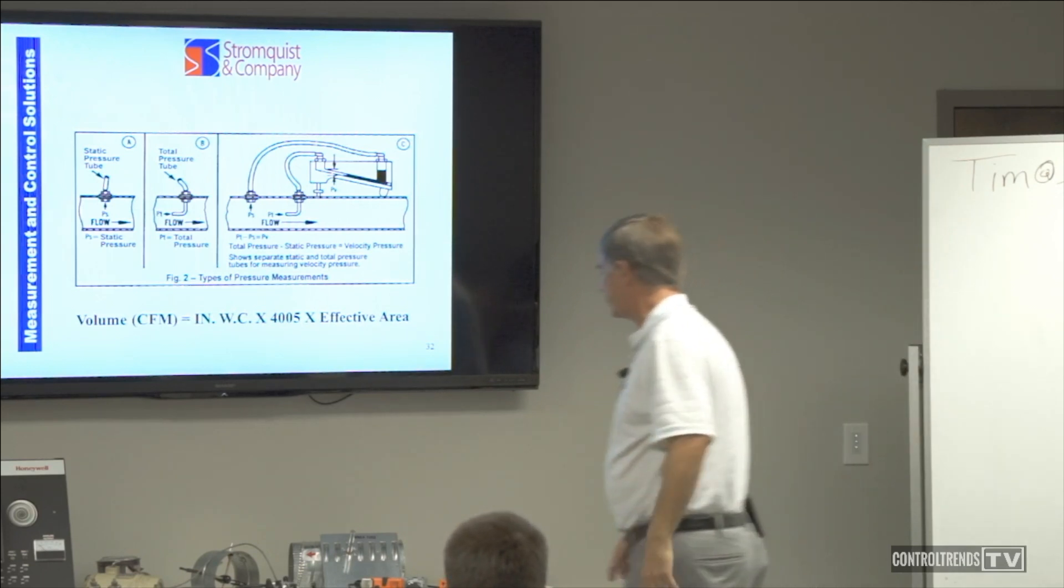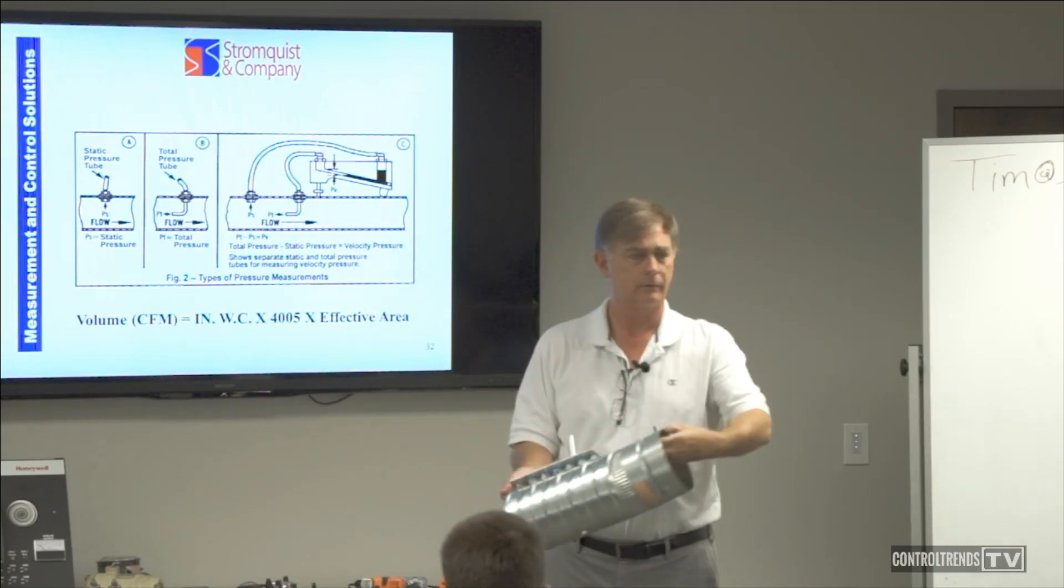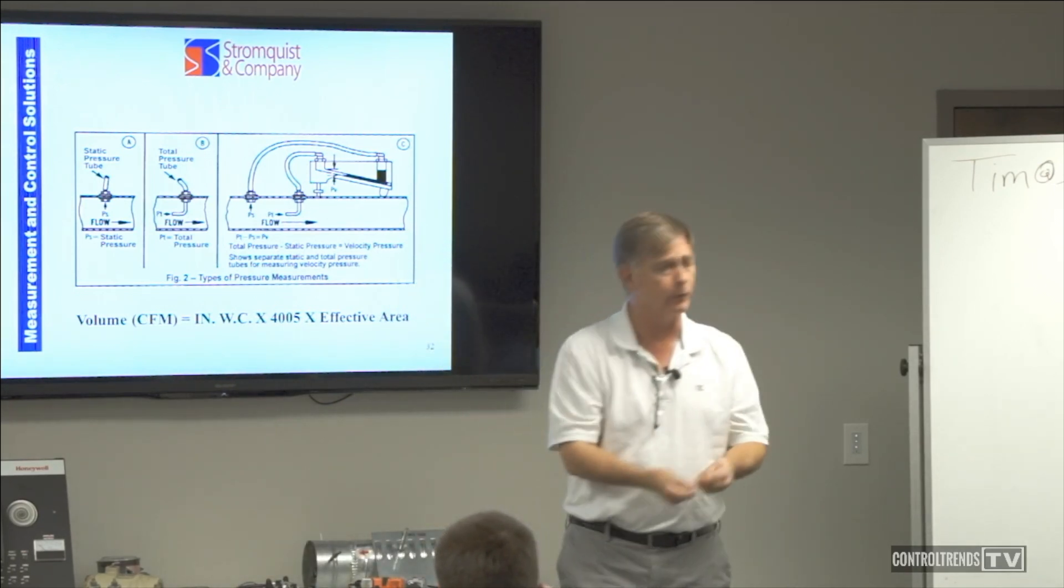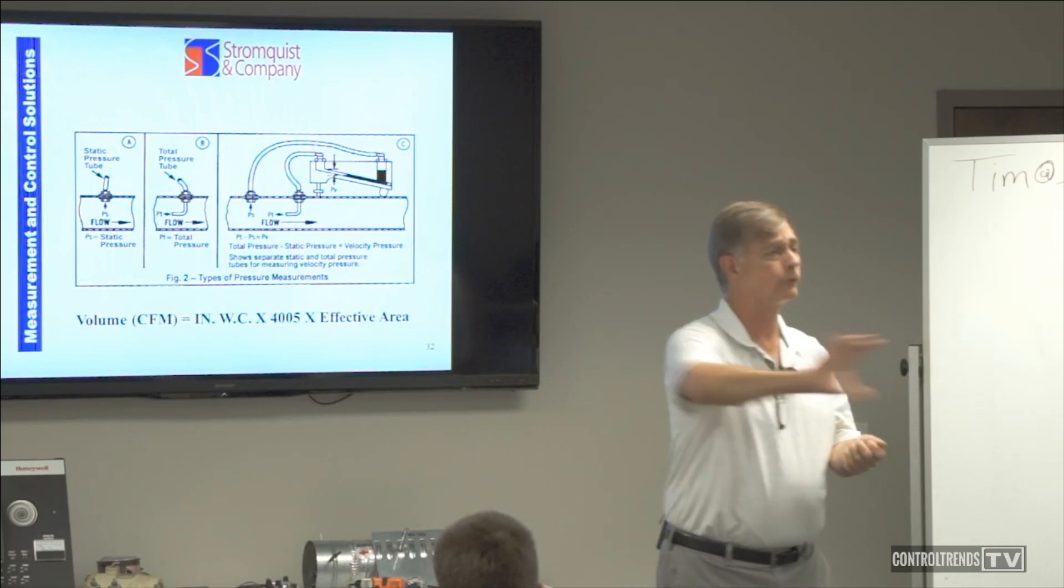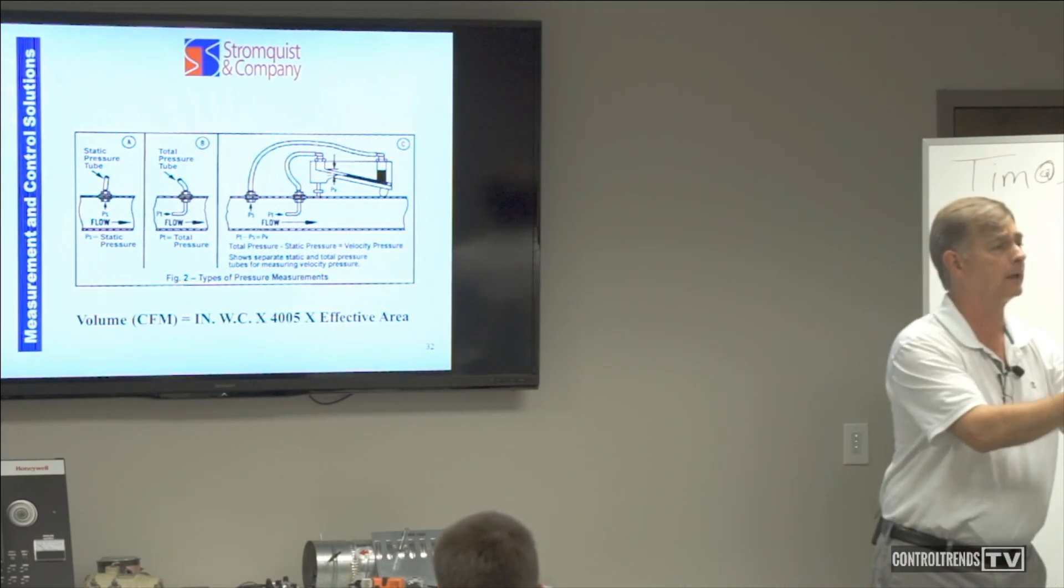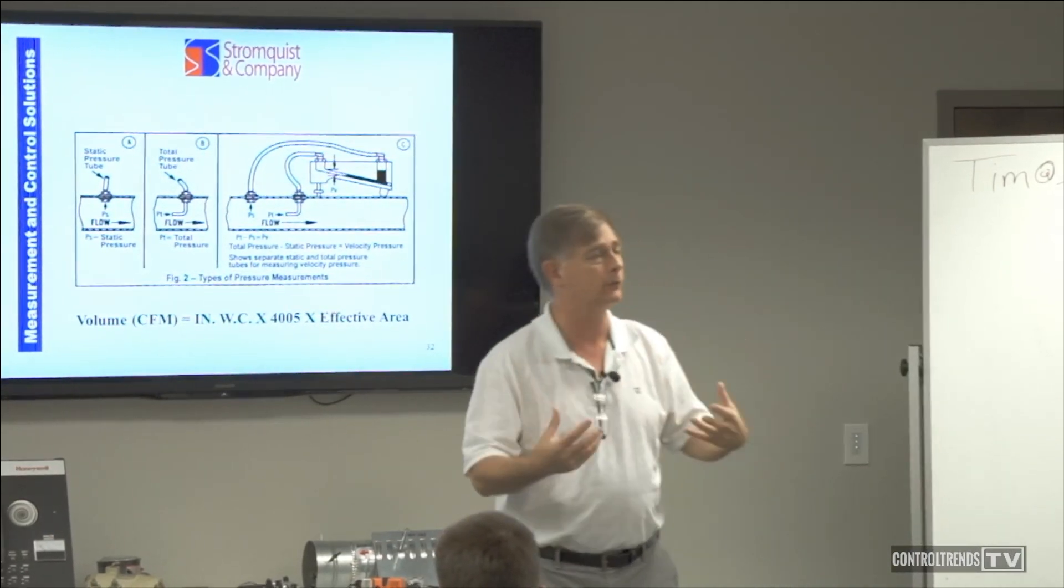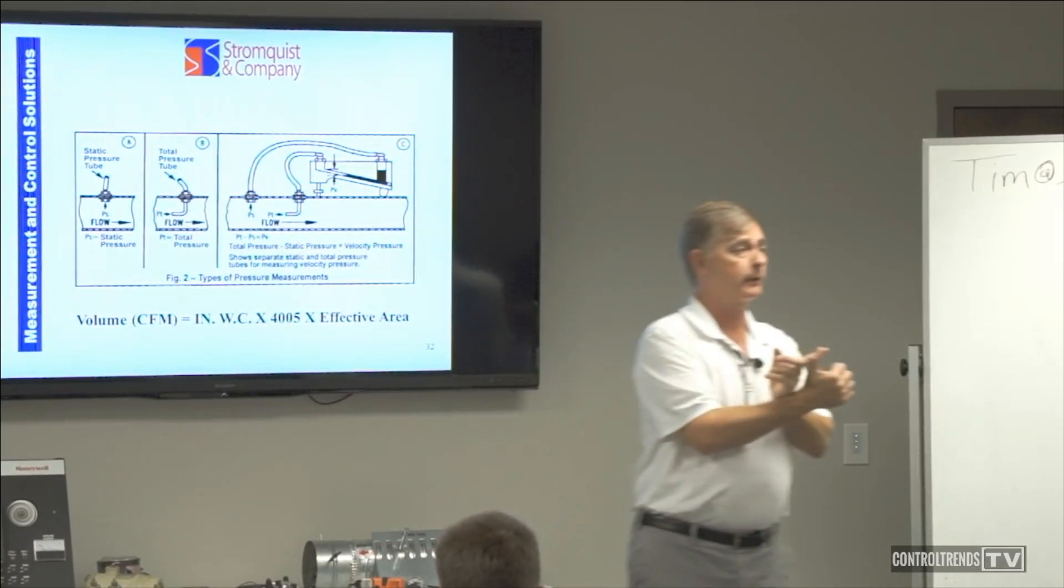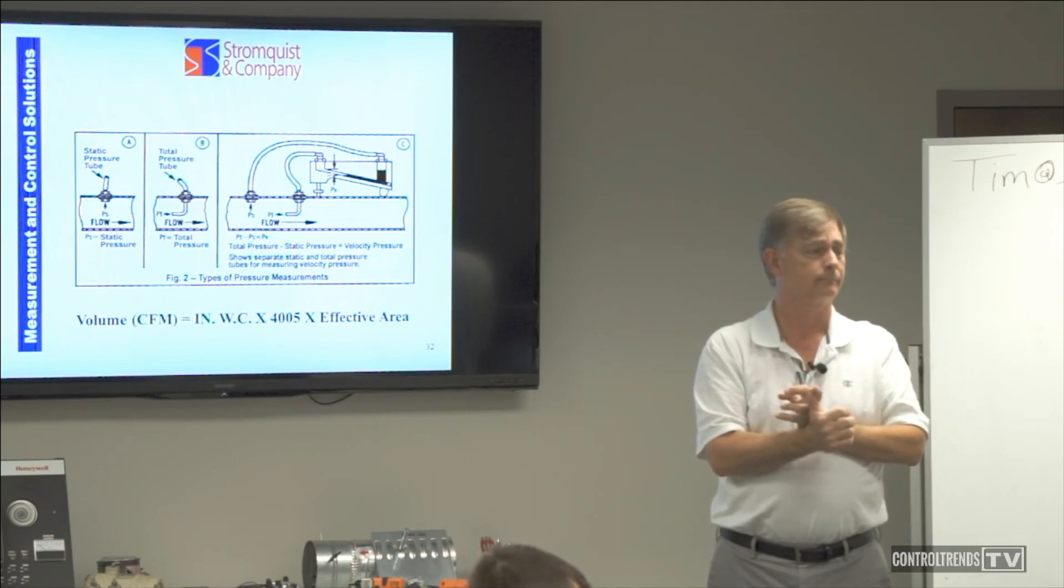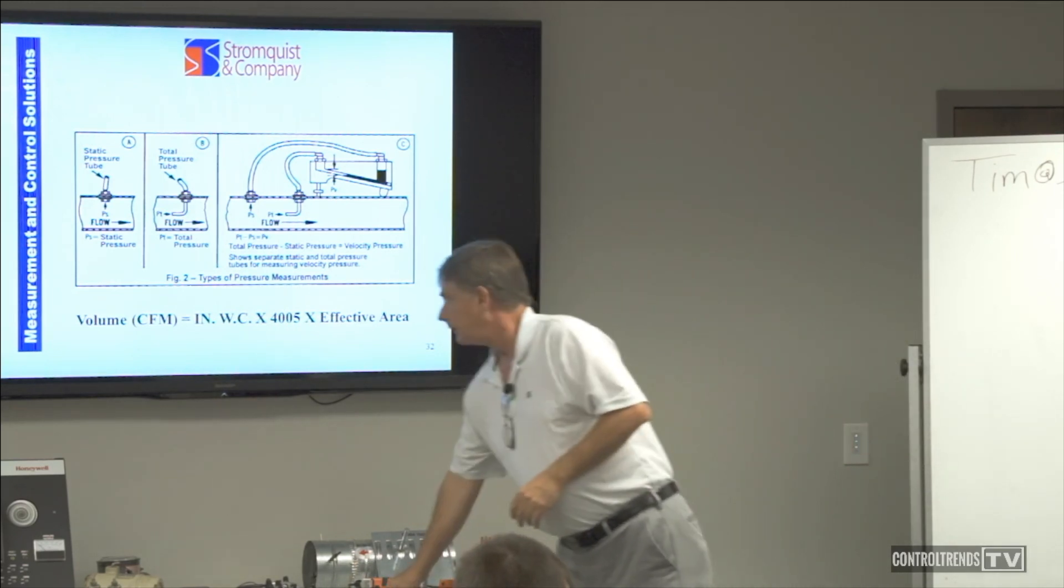You could go to a VAV box that has your high and low tubes coming out of it, and you could measure it there and know how much air is going through that box. Call Joe up at the computer and say, 'Hey, what's the computer saying is my airflow?' You can measure it right there and verify, rather than just assume that everything is right. Measurement is really important, and then verification. Well, your Phoenix valves, checking all those, trying to get all that air balance out right. Yeah, absolutely. That's a task in itself.